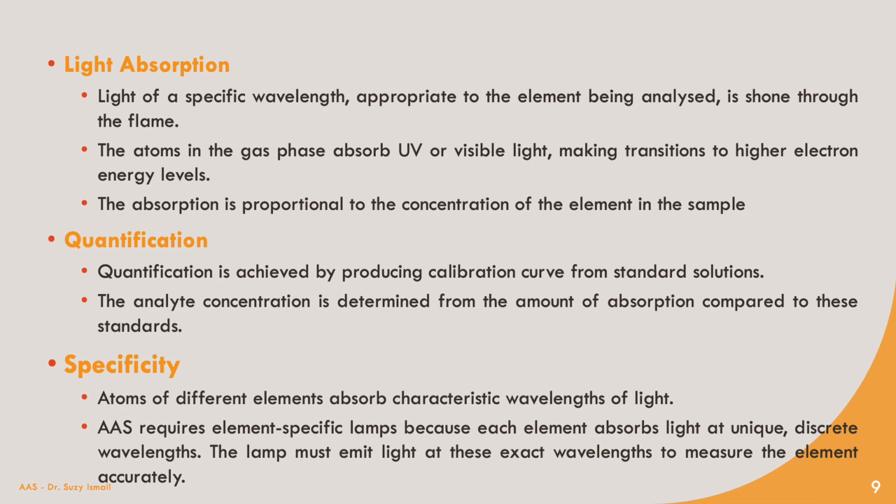And this absorption causes the atom to move to a higher electron energy level. The important part here is that the amount of light absorbed is directly proportional to the concentration of the element in the sample. So more absorption means higher concentration of the element. Understand or not? Because if your solution contains a lot of copper, for example, the copper atoms will be freely in the flame.